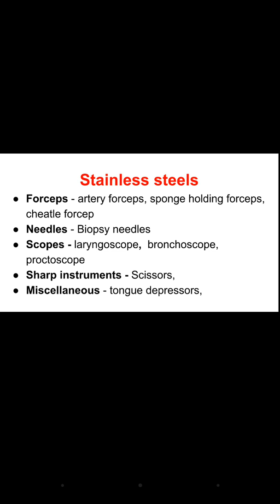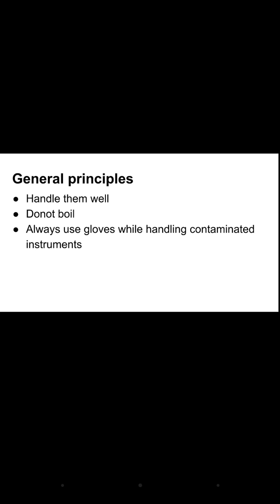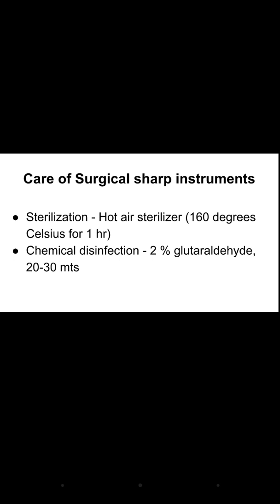What are the general principles? Handle them well. Do not boil them, because their sharpness will become dull, and, for example, a scissor will not be of any use. Always use gloves while handling the contaminated instruments. Most commonly the forceps are used during minor OT operations or procedures. So always use gloves while you are handling the contaminated instruments, because they are contaminated with blood or tissue. For sterilization, a hot air sterilizer at 160 degrees Celsius for 1 hour is used. And as a chemical disinfectant, we can use 2% glutaraldehyde, that is Cidex solution, for 20 to 30 minutes.